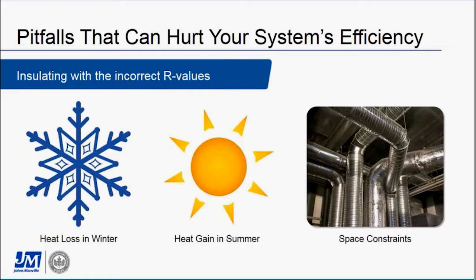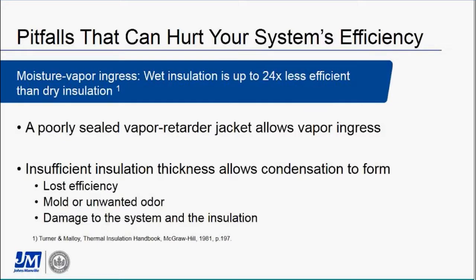For example, under certain conditions, thicker duct insulation is required to prevent condensation on insulated ducts, or there might be times when insulation should be thicker for improved thermal efficiency based on prolonged winter or summer conditions. For a system that requires a low-perm vapor retarder facing to help prevent condensation, the vapor retarder needs to be properly sealed with a vapor retarder tape or mastic.